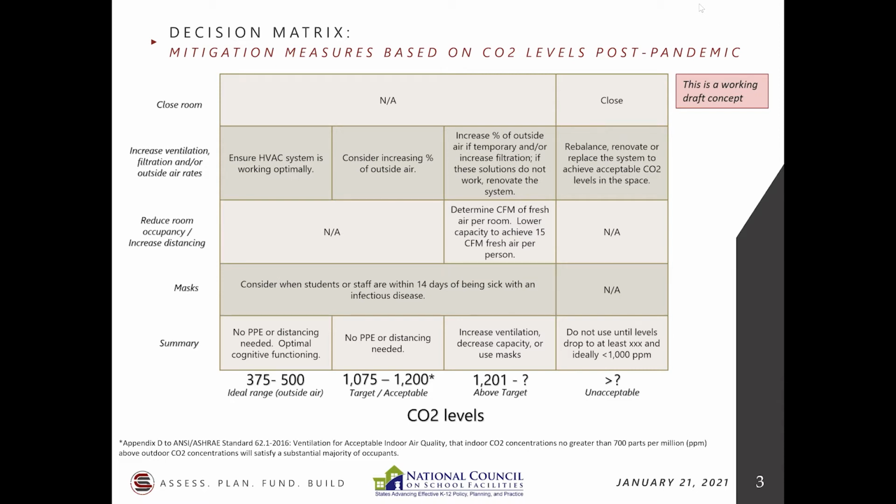All you need is the generation rate and the equilibrium concentration of CO2 in the classroom. There are simple equations to lay out very quickly what you get in terms of CFM per person. 15 has been what we've had in the past, 13 to 15 CFM per person. I'm not sure that applies anymore right now.